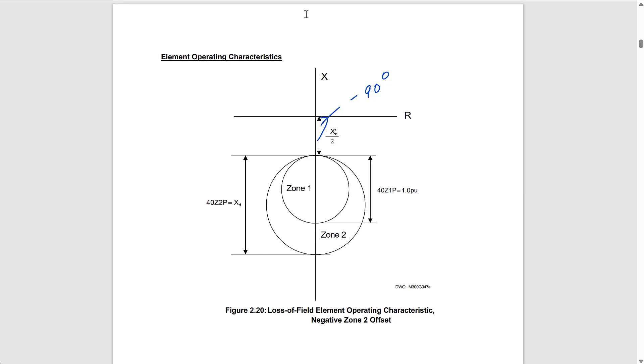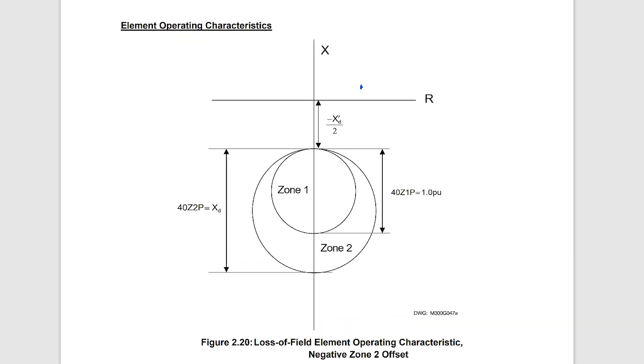We have two zones because the trajectory of the impedance from the load impedance to the impedance after the loss of field condition depends on the initial loading of the machine. For a heavily loaded machine, the trajectory of the impedance starts somewhere in the load region and falls to somewhere around the zone one element. For a lightly loaded machine, the trajectory looks different — the load impedance is farther out, and the trajectory looks something like this.